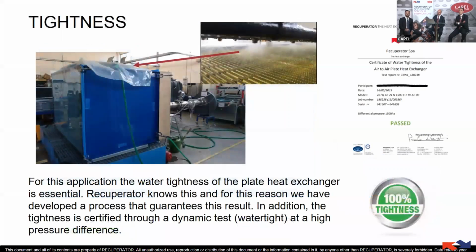Another important point is the tightness. The tightness that we've seen before is to avoid any type of cross-contamination, but it's also needed to avoid any type of leakage of water in this case. We can test the plate heat exchanger for leakage thanks to a tunnel that we have implemented, where we can test the tightness in terms of water of the heat exchanger with a pressurized system. You can see this is a channel, we have a fan, we put the heat exchanger under pressure, we shower the heat exchanger really a lot, let's say 1000 liters per hour, and then we check if there are leakages. And we ship the unit only if the unit is completely tight.